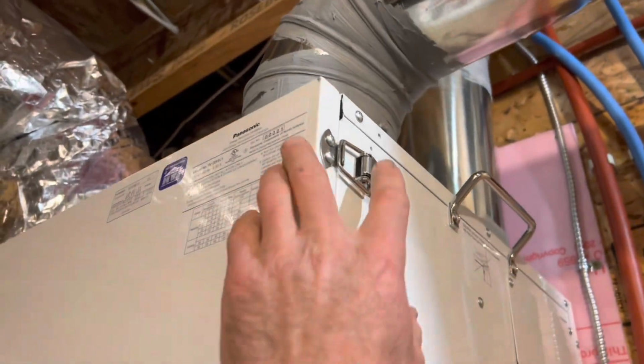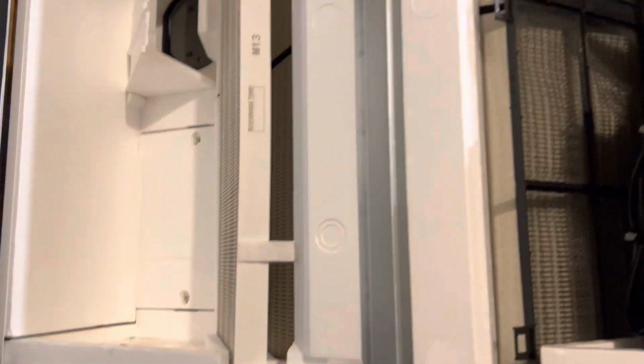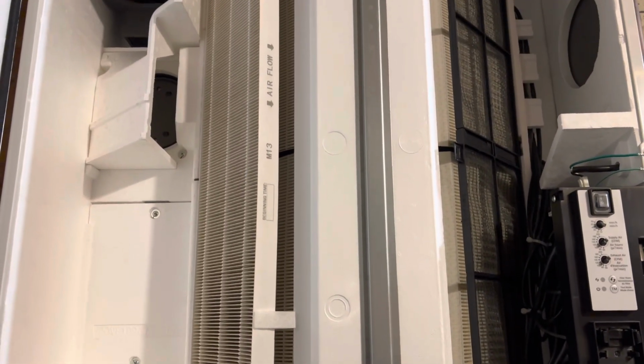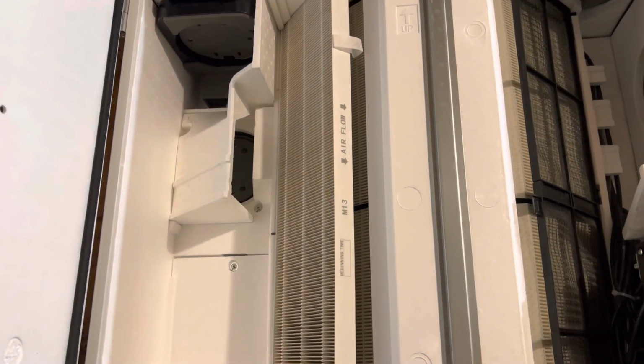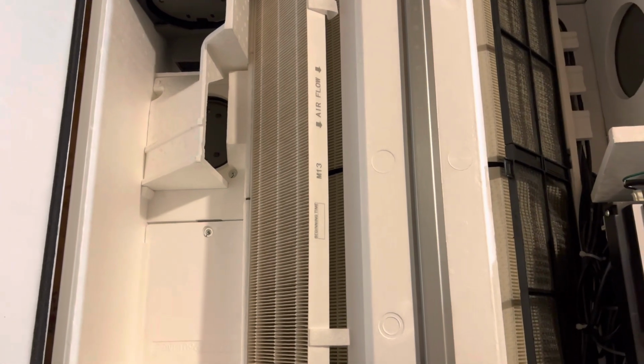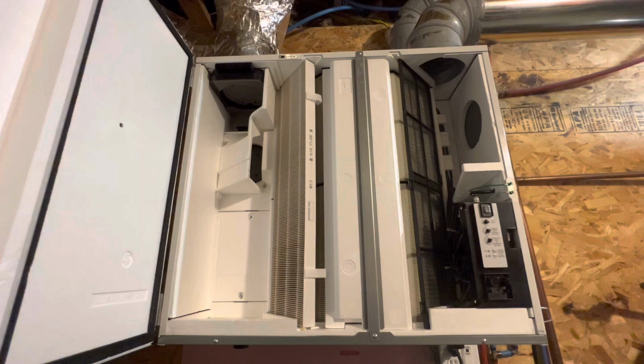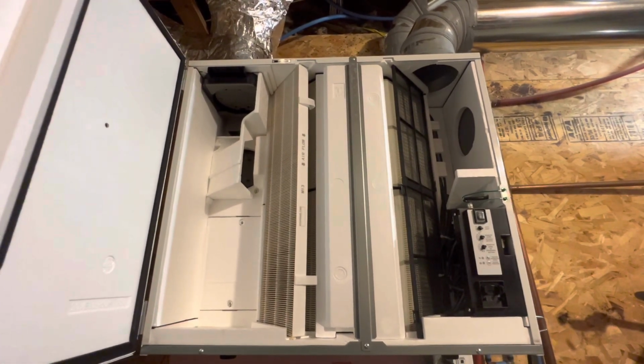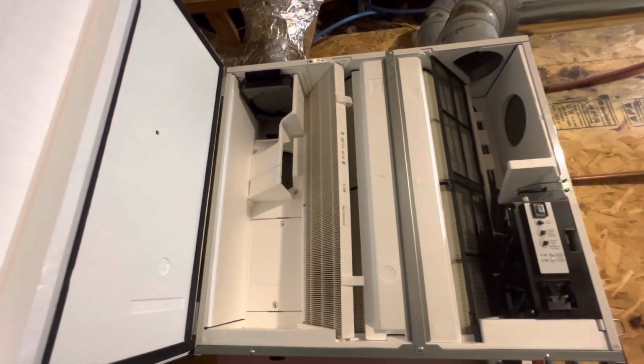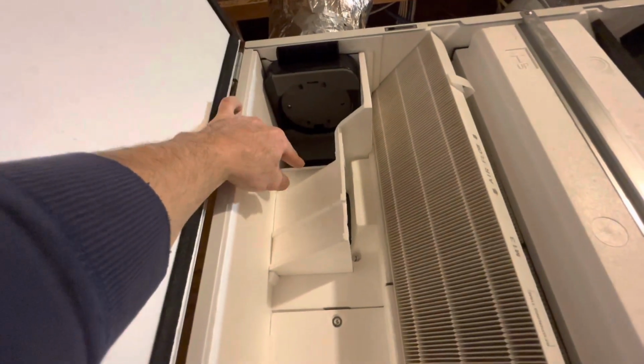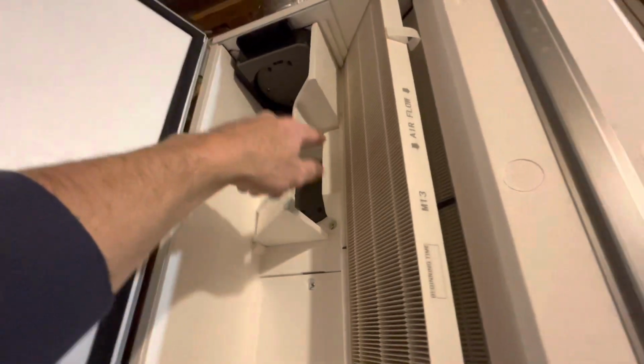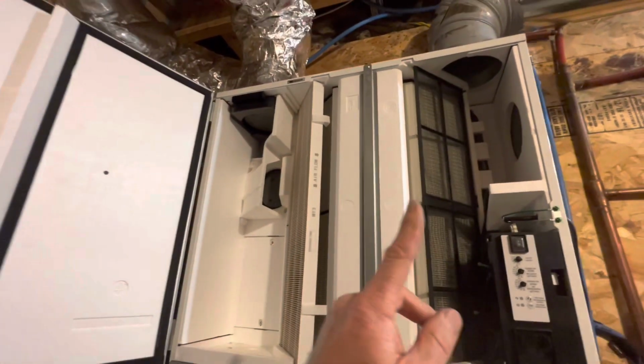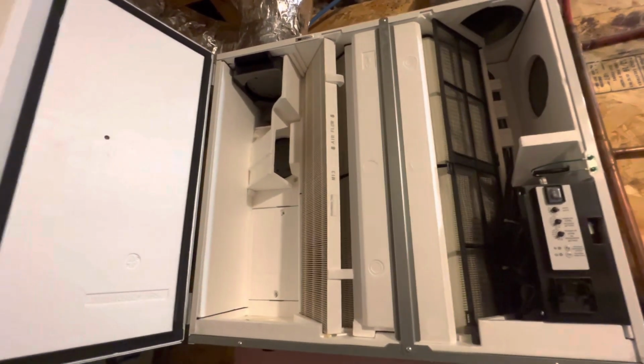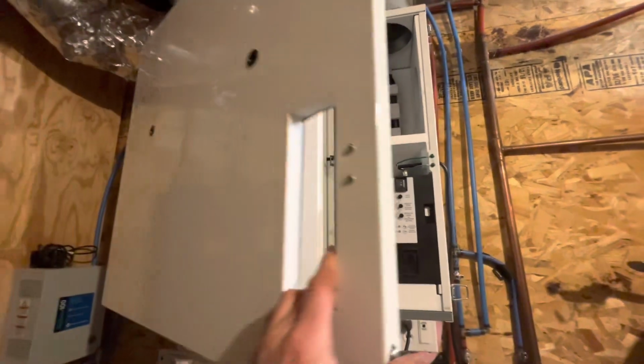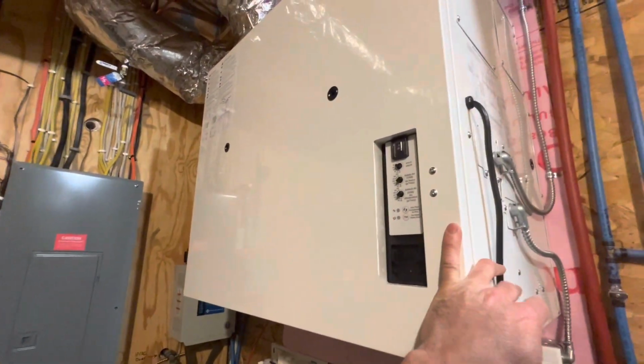One thing I didn't show you is that in the wintertime, the unit has temperature and humidity sensors built in, so if it's very cold out, it has an automatic defrost built into it. When the temperature gets below a certain level, it will shut this damper and the other damper and open this damper, and it will just recirculate air through the ERV with the house air to defrost itself. Like I said, it's got a table in the manual that explains how much it does that recirculation based on the temperature.